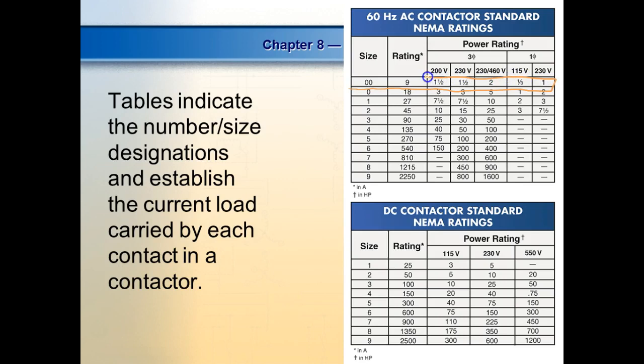Then it says it can run a 1.5 horsepower three phase motor at 200 volts. It could run a 1.5 horsepower three phase motor on 230, and in 460 it could run a 115, 1/3, and then 230 single phase one. We okay? That makes sense. This is real hard to see.